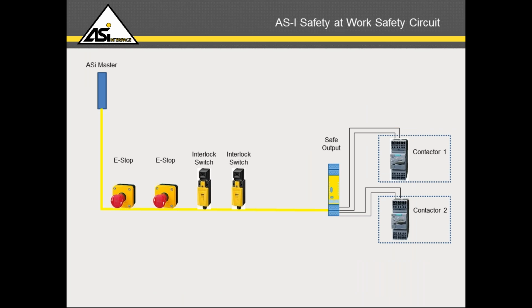So let's look at the same type of safety system using AS-i Safe. As you may already know, if you have experience with AS-i or if you attended our last webinar, you can run safe and standard signals on the same AS-i cable. It doesn't matter, they can all live together on the same cable. Devices are attached to the network in whatever network configuration is convenient. The network can be a ring, star, linear, or a combination of topologies. AS-i really doesn't care, and it's the same in AS-i Safe.